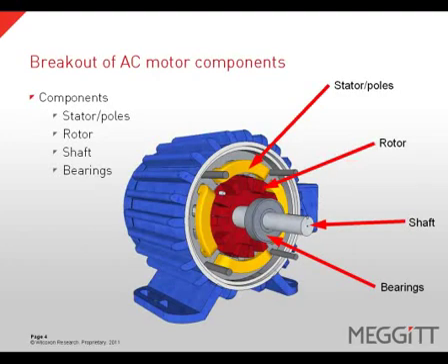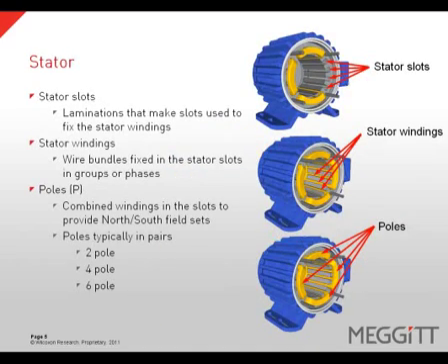To understand how electrical motor issues manifest themselves in the vibration world, it is important to first understand the components that make up an electrical motor. An electrical motor is made up of a shaft to which the rotor is mounted, riding on bearings. The rotor assembly rotates within the stator. A stator is a part of the motor housing that has laminations which make the slots used to fix the stator windings. The windings are a series of wire bundles in a stator slot that create groups or phases. We also have stator poles — windings in the slots that are combined to provide a north-south field set. Poles are typically in pairs such as two-pole, four-pole, or six-pole motors.